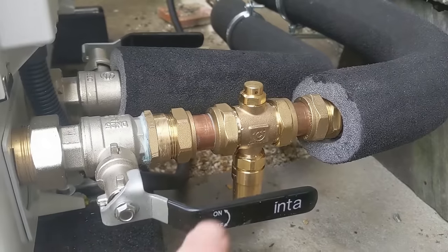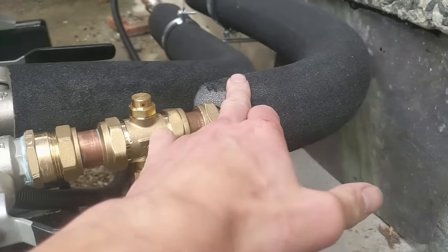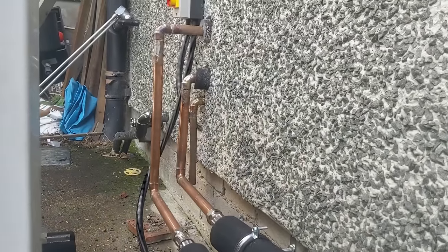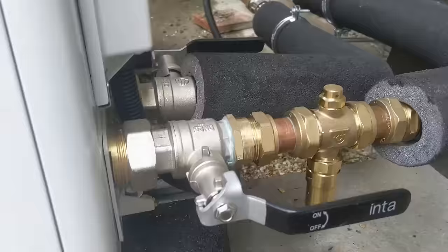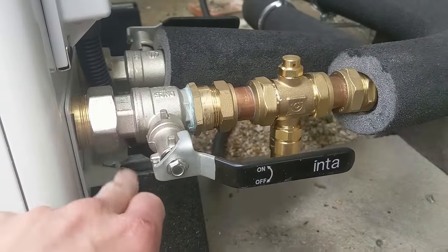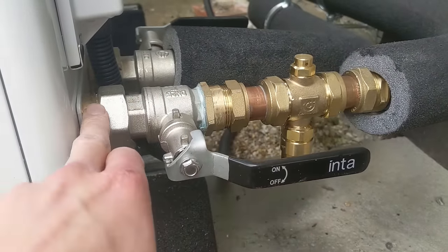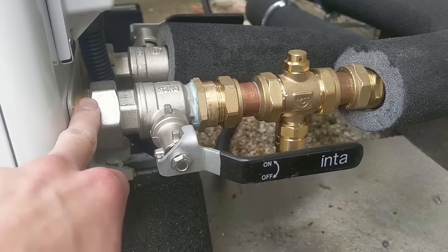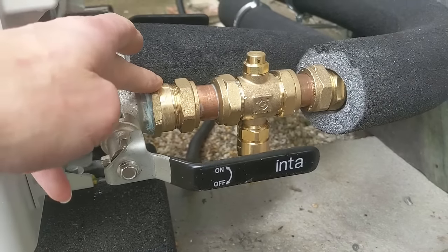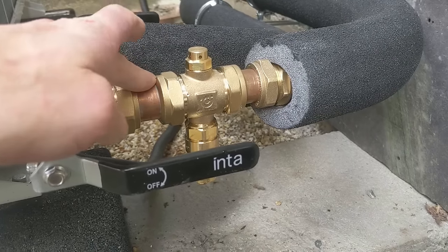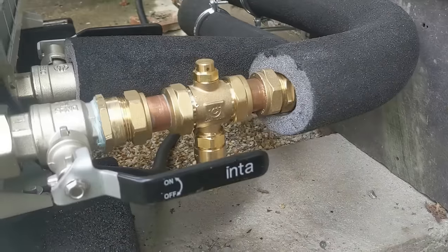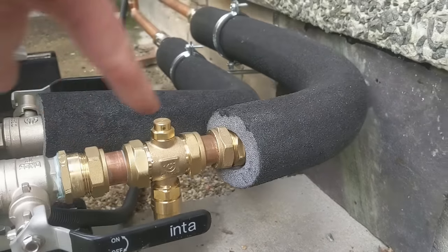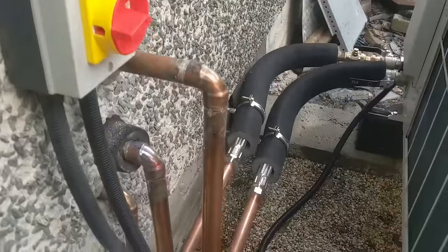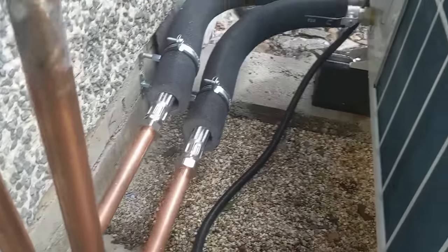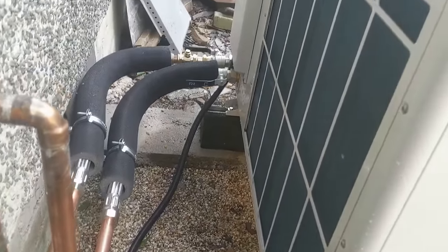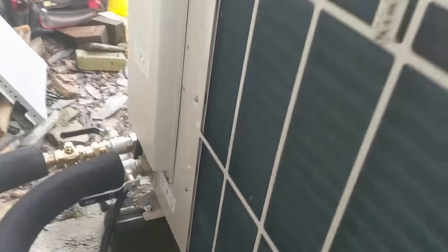So I've got this antifreeze valve here connected onto flexible hoses that then go onto 28mm pipework there. I use these Inta valves. Quite a nice valve. It's got the 1¼" flat face there that goes to a 1" here, and then I put that into a bit of 28mm and then on through the compression fittings through the antifreeze valve and then onto the flexible connectors. And that's the electrical. This obviously needs to be all clipped up and attached onto the wall, but it's just connected temporarily for testing. It's super easy, this heat pump, to connect up.